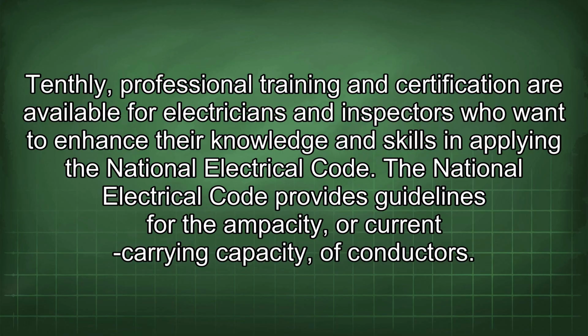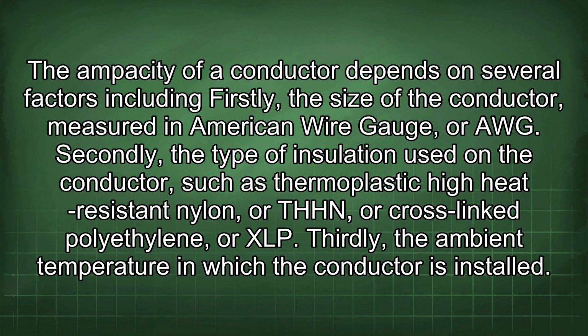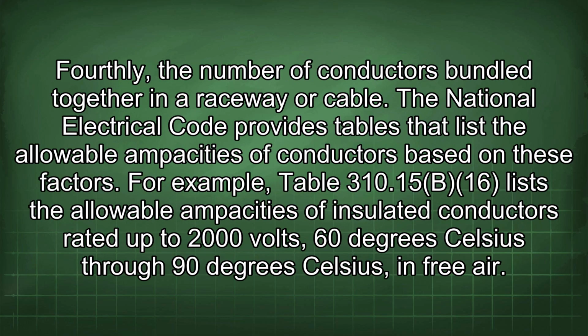The National Electrical Code provides guidelines for the ampacity, or current carrying capacity, of conductors. The ampacity of a conductor depends on several factors, including, firstly, the size of the conductor, measured in American Wire Gauge or AWG. Secondly, the type of insulation used on the conductor, such as thermoplastic high heat-resistant nylon or THHN, or cross-linked polyethylene or XLPE. Thirdly, the ambient temperature in which the conductor is installed. Fourthly, the number of conductors bundled together in a raceway or cable.